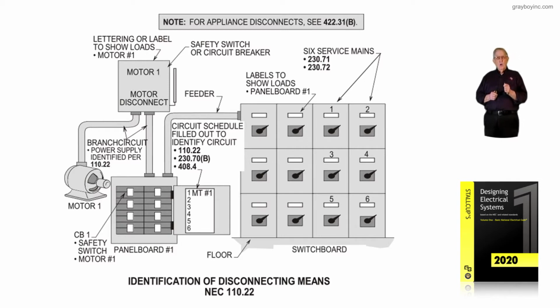Now, the note 2 states, for labeling suggestions and recommendations, see the ANSI standard Z535.4 for guidelines pertaining to designing safety signs and labels to provide the warnings that the NEC calls for. Now, if you notice right above the equipment, we have: electrical equipment shall be marked in the field to warn workers of electrical arc flash condition.